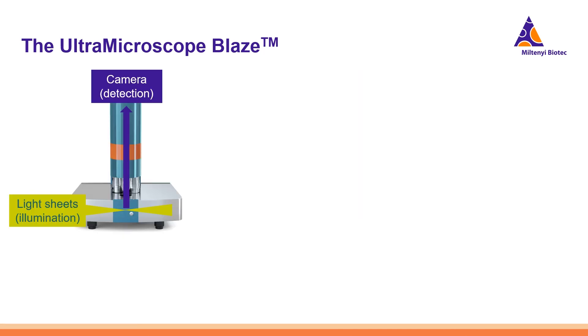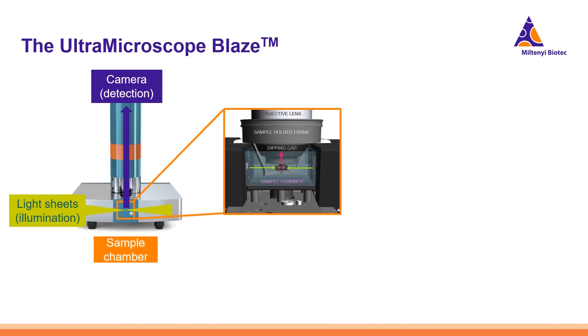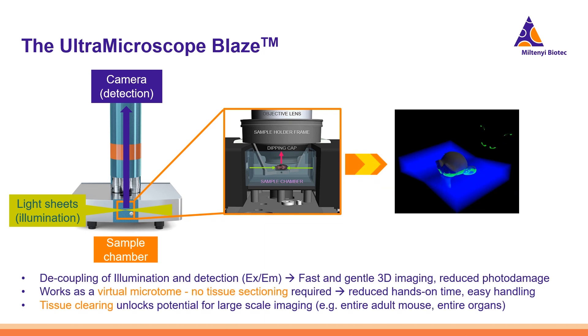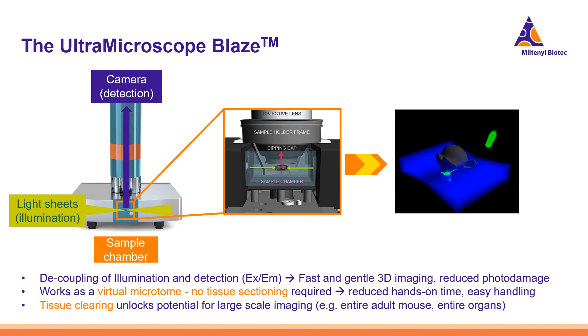In the Ultra Microscope Blaze, the process of generating a 3D image involves illuminating optically cleared samples from the side while capturing the signal using an objective above, as illustrated in the left panel. Within the imaging chamber, a thin sheet of light is used to illuminate a fluorescently stained and cleared sample. To construct a complete 3D image, the sample is gradually moved through the sheet of light. By capturing a series of images at different depths, a Z-stack is obtained, then the images are processed and rendered into a comprehensive 3D representation.